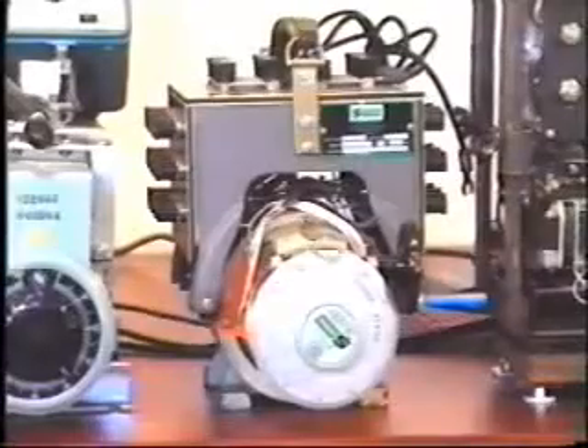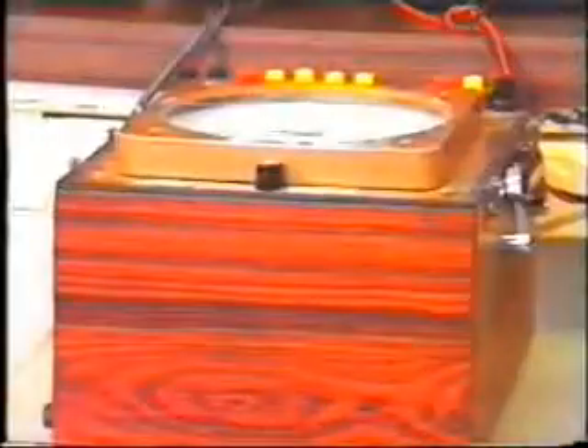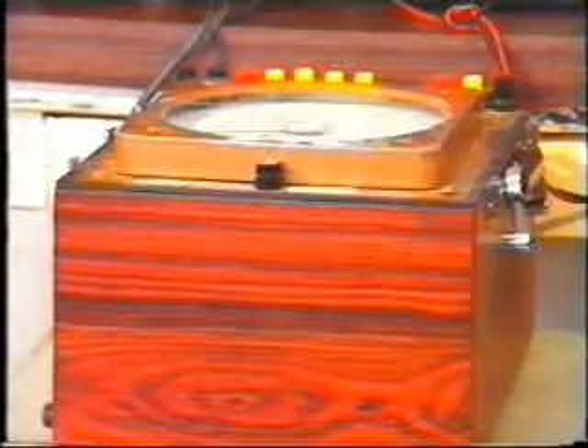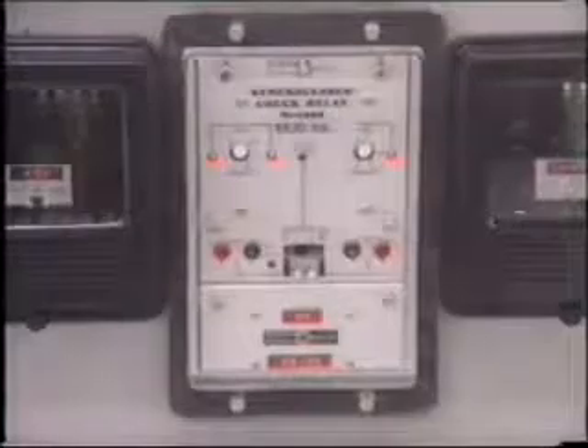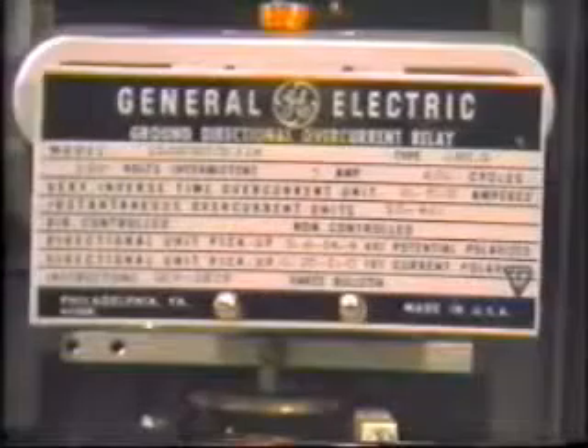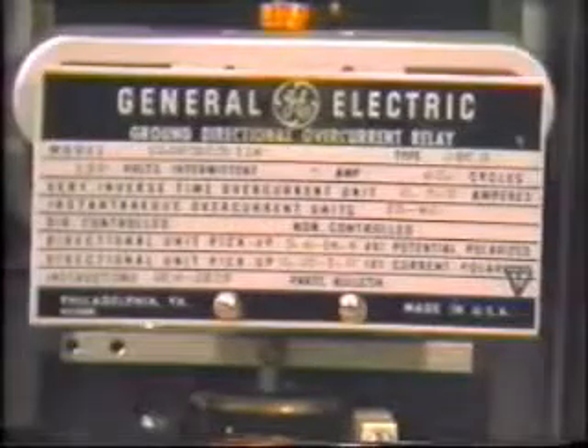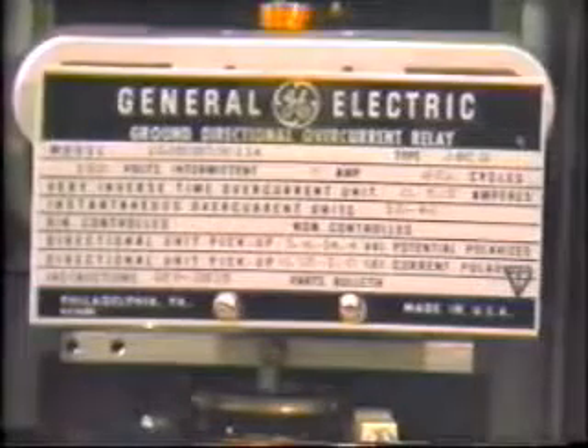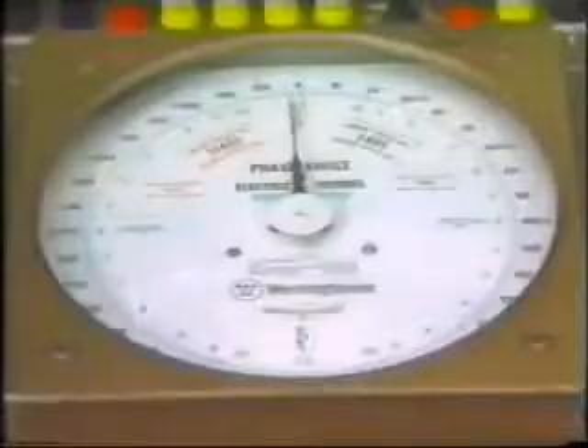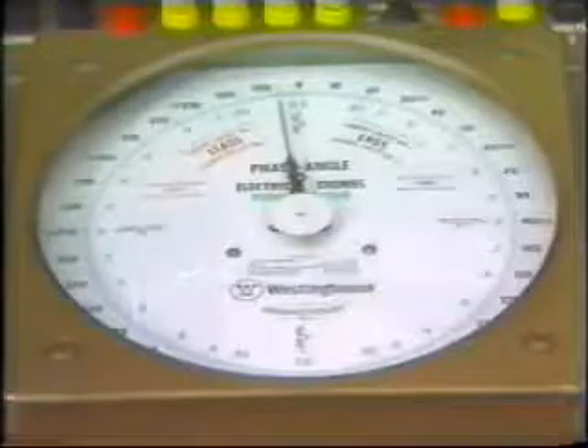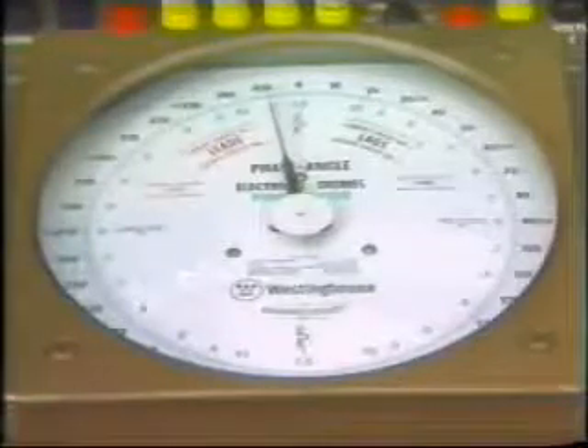Traditionally, a phase-shifting transformer and phase angle meter have always been used when out-of-phase voltages are required. For example, a synchro closer check relay. This setup may also be used to check the maximum torque angle of a directional overcurrent relay. This is done by shifting the phase angle of voltage with respect to the test current.